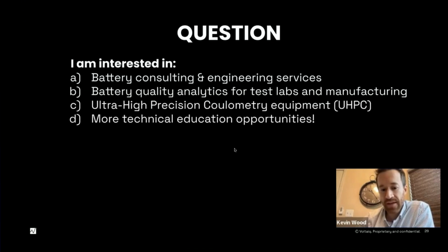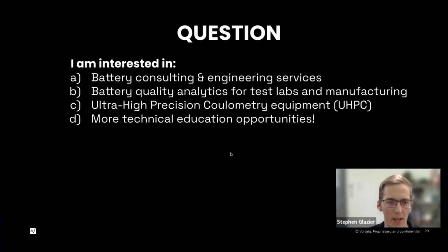Once again, I wish I could give you one silver bullet of how you set up a test and collect all this amazing information on DQDV and UHPC. You have to think about your system, the battery that you're testing, and also if you're not using a NOVONIX piece of equipment. And even if you are, you have to think about what the resolution of that equipment actually is.